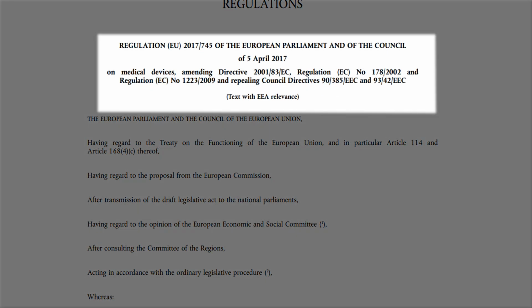If you still have medical devices on the market that were correctly CE marked before the date of application, you can keep them on the market as long as you basically don't change them. And those MDD devices are allowed to stay on the market until the 31st of December 2028, or the 31st of December 2027 if it is an implant or Class 3 device. Those were the major things in the MDR that I wanted to highlight in relation to the PRRC role.